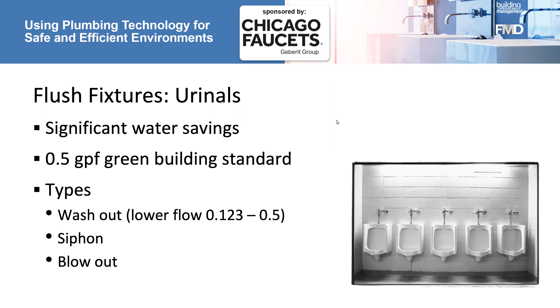Similar to toilets, ensuring the proper flushometer is selected for the proper corresponding fixture type is important in the selection process for new construction or any upgrades or renovations when it comes to urinals. Unfortunately, the drawbacks with any flushometer remain the same, with potential for non-calibrated and faulty devices, which can result in decreased efficiency and loss of water savings. Many of the urinal manufacturers offer a sleeker all-in-one model with the flushometer integrated into the porcelain housing, but this can lead to an increased cost because now you have to replace the whole fixture versus a couple components. So that could increase the difficulty of troubleshooting of potential issues.